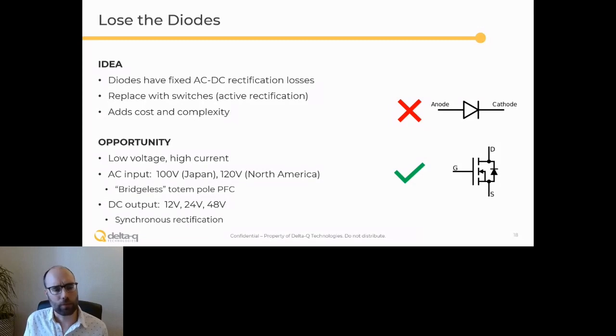But this is an opportunity, particularly where you have low voltage and therefore high currents. So on the AC side, particularly in Japan and North America with lower input voltages, a bridgeless or totem pole power factor correction circuit may make sense. At the DC output with synchronous rectification, this may make sense, particularly at 12 volts, 24 volts, maybe 48. You can still have synchronous rectification in a 400 volt system, but at that point, you're no longer talking about saving 2 or 3% efficiency - you're talking maybe 0.5%, marginal gains.